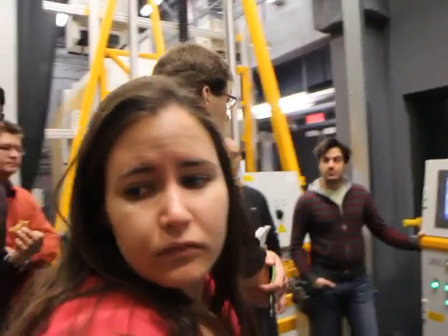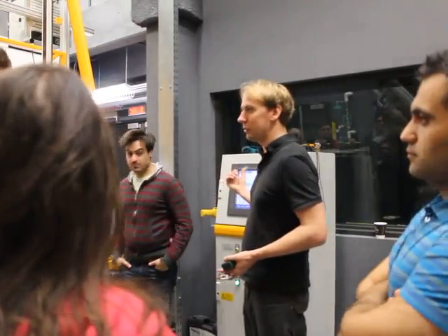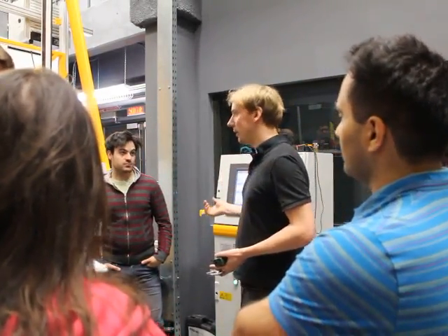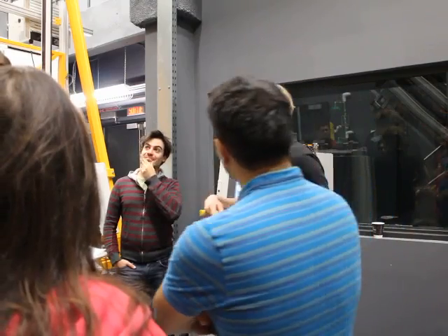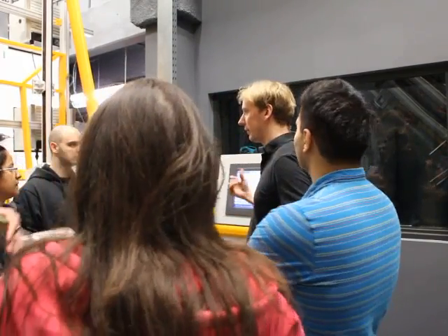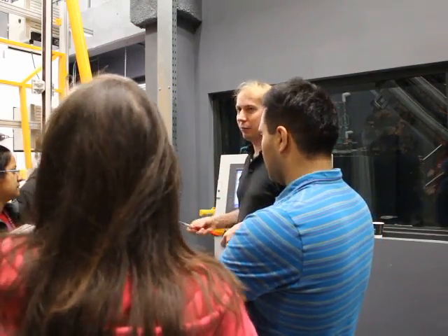So that was already the area from yesterday. I don't know, the selector might always change. I would just set the ventilation to about 50%. Okay? What we also can do now already is to switch on the data acquisition. I will not do that because at the same time I want to run the scan after we start the test. So we will do the scan during lunchtime because it's automated. We don't have to wait here.